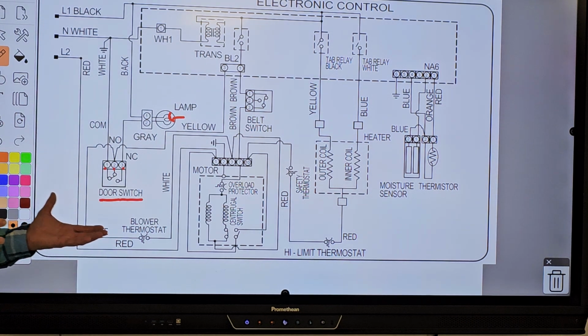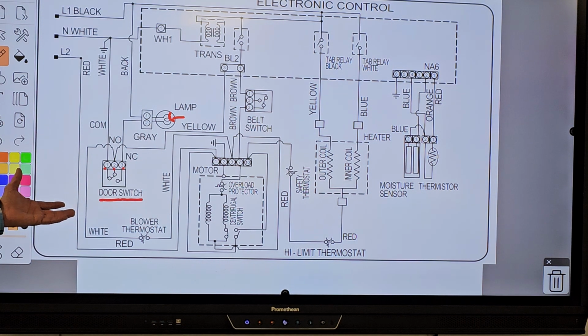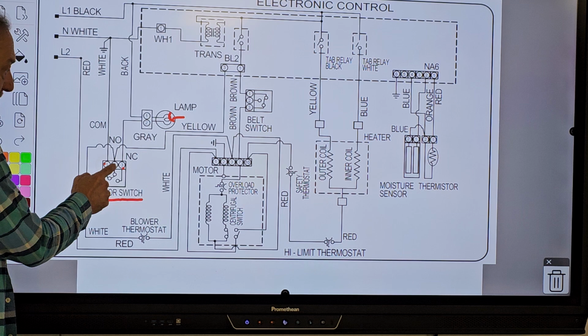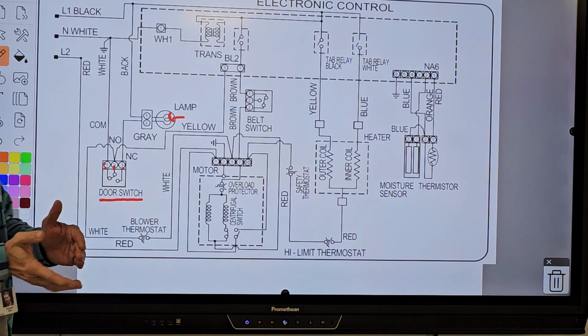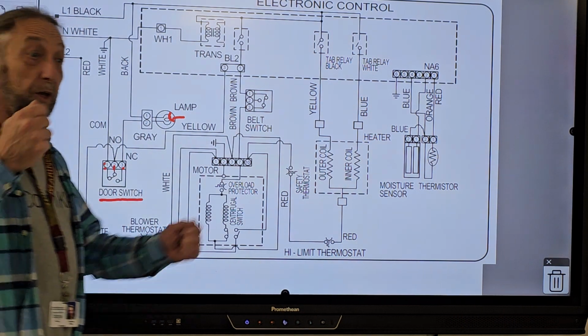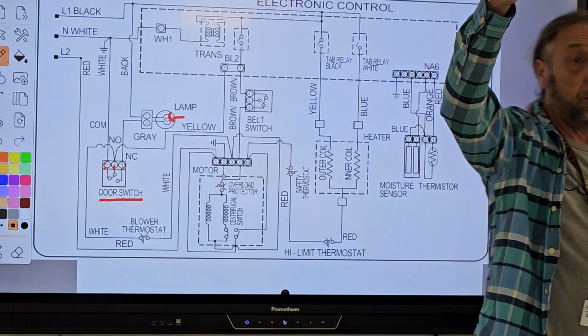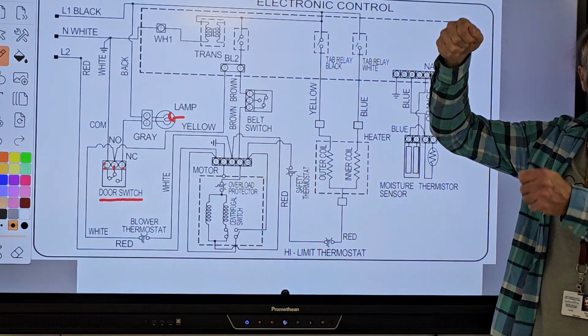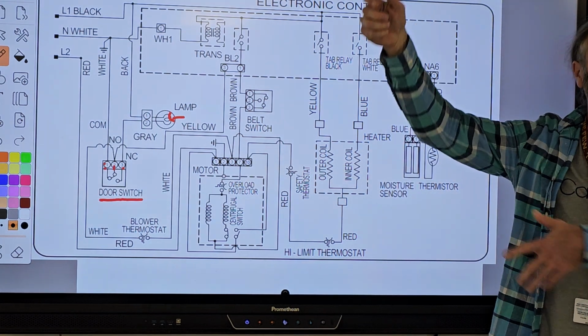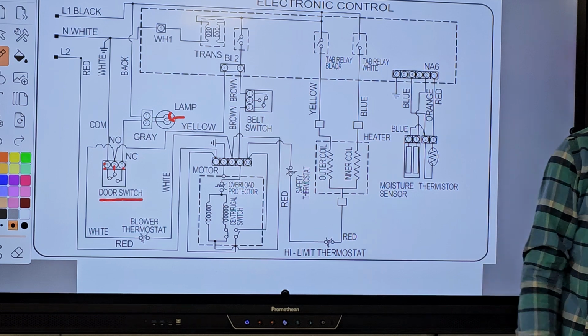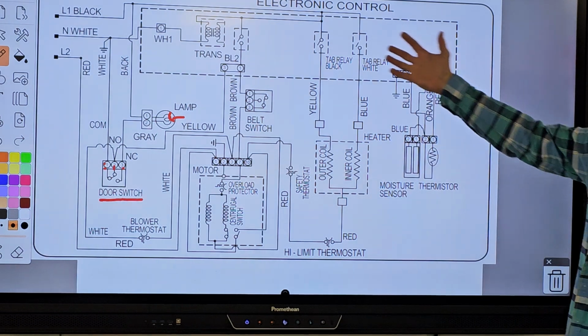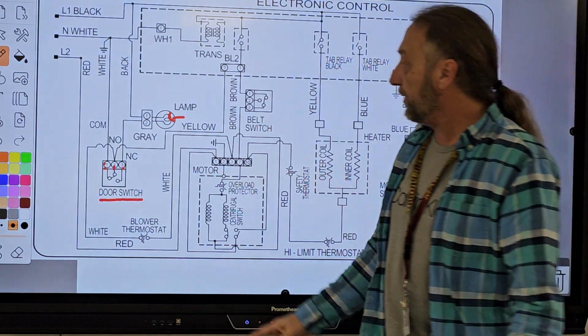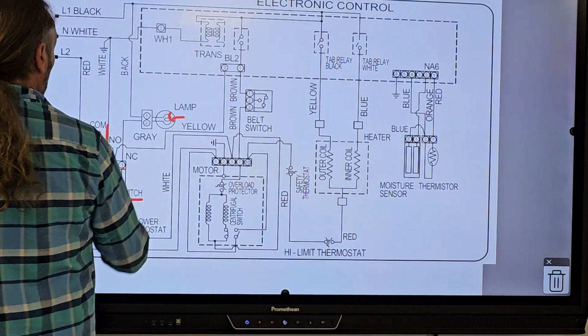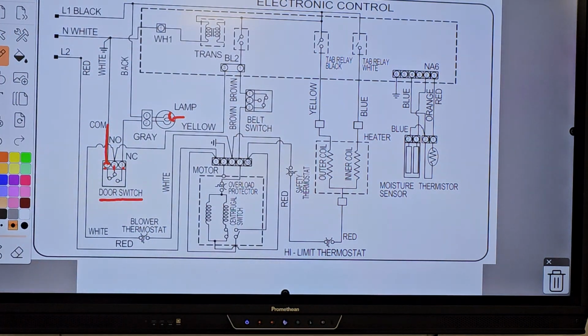What 2 terminals on that switch need to be closed in order for the dryer to run? 1 and 2. So where do they go on the board, where I would tell you put your meter here and here, because if you put your meter on these 2 wires on the board, it'll check that switch for me. Where on this board? If you followed pin 1 backwards, where does it actually touch the board?